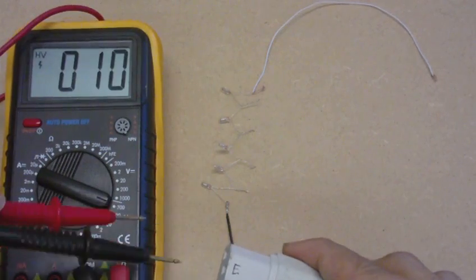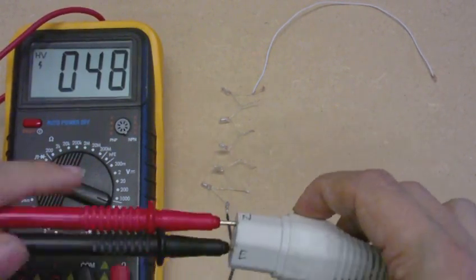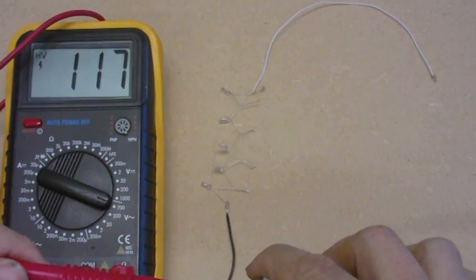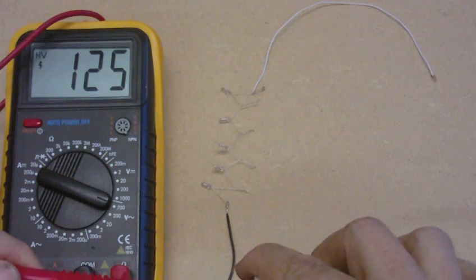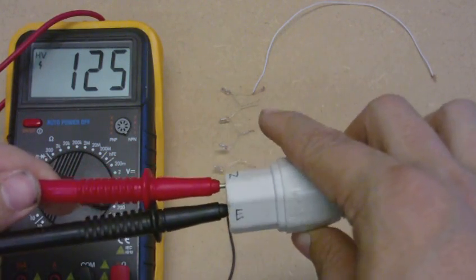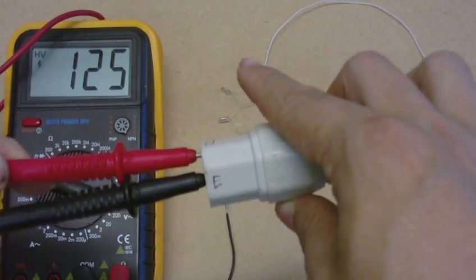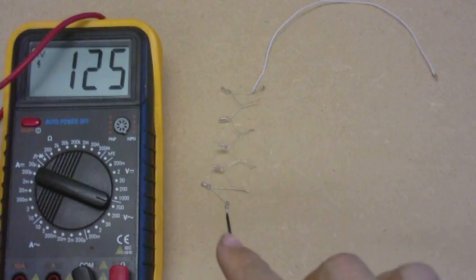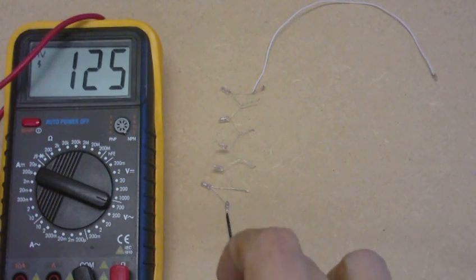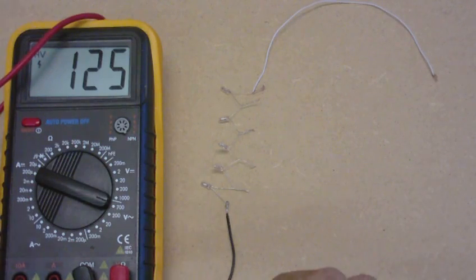But now if I connect it between the earth and the neutral, can you see that? This is earth and neutral, yet I'm getting 125 volts on the meter. It seems to change completely at random. Last time I did this test it was about 60 volts, now it's at about 125 volts, which is kind of strange.